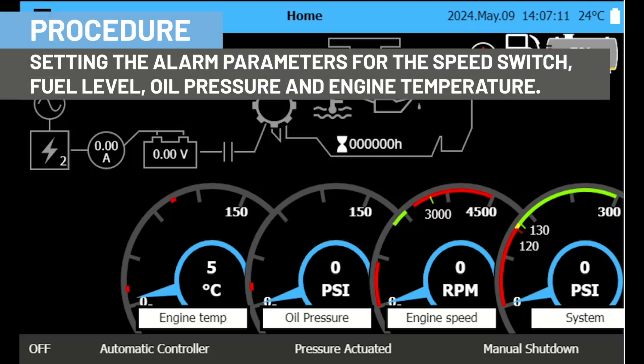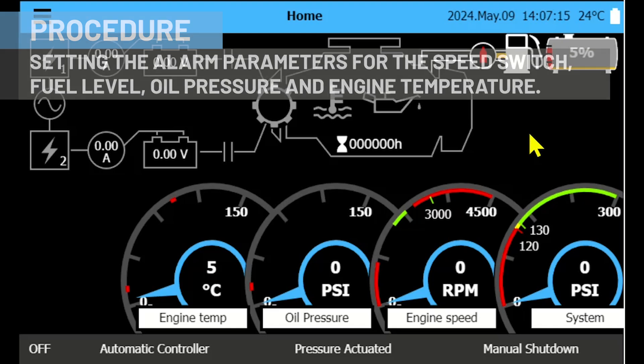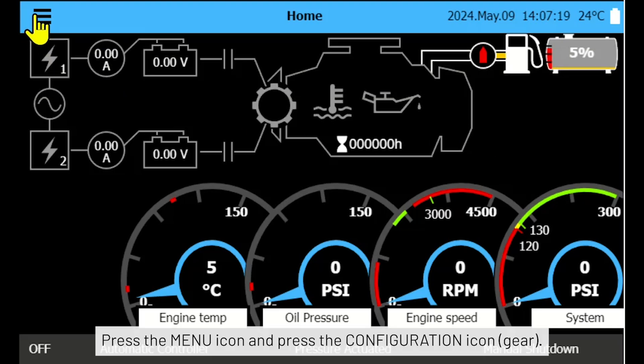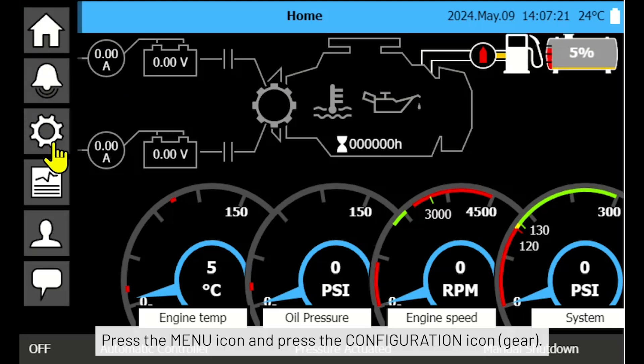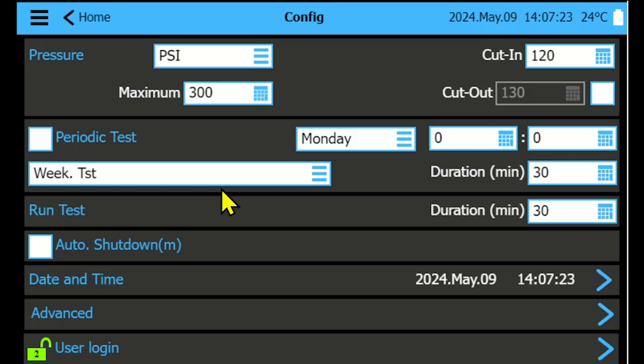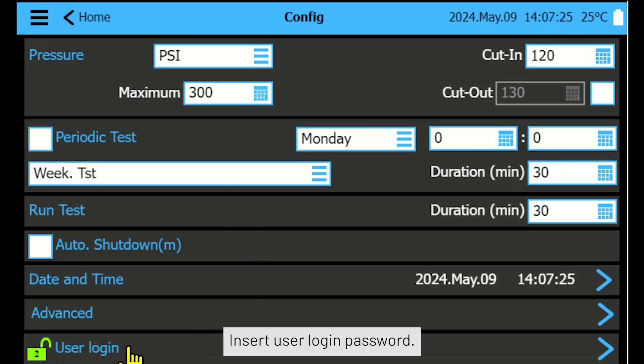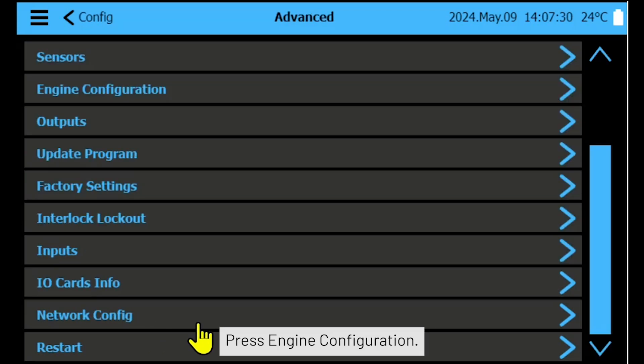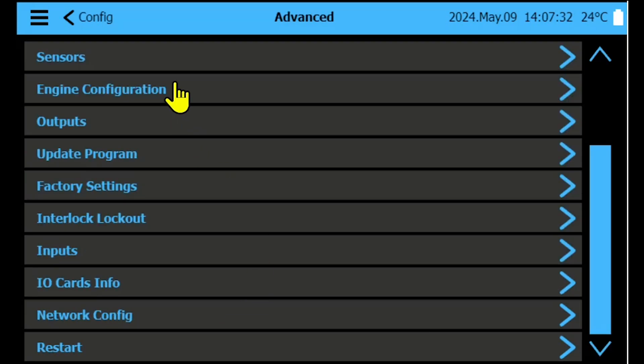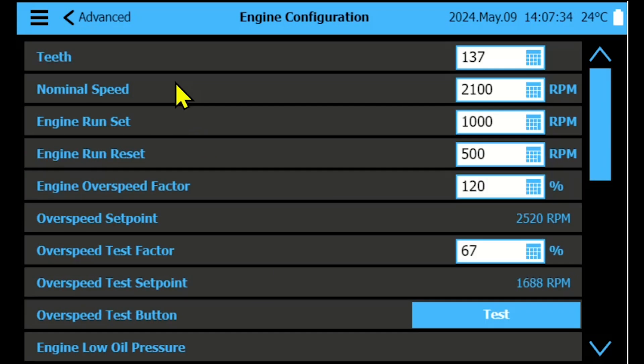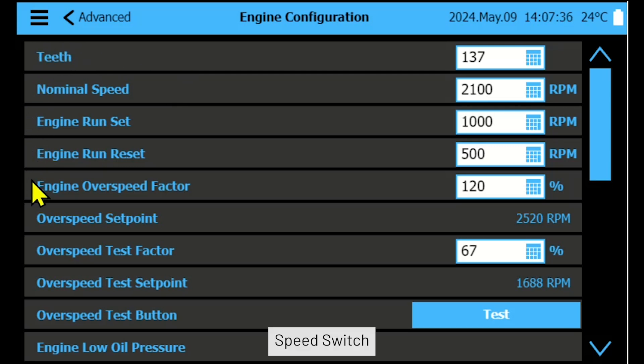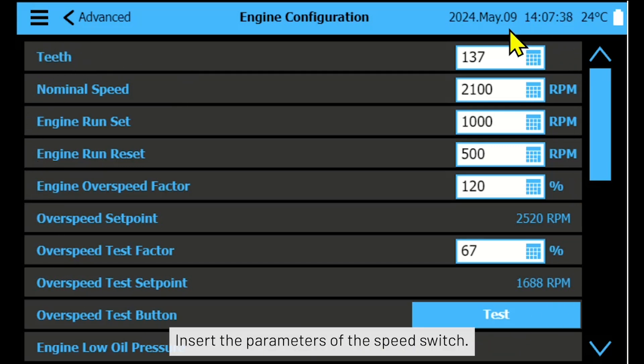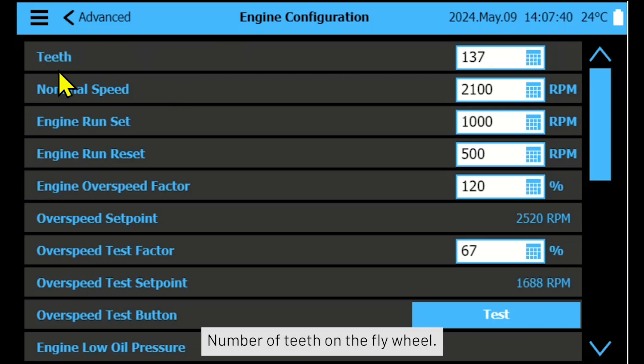Setting the alarm parameters for the speed switch, fuel level, oil pressure, and engine temperature. Press the menu icon and press the configuration icon. Insert the user login password, press Advanced, then press Engine Configuration. Speed switch: insert the parameters of the speed switch, including the number of teeth on the flywheel.